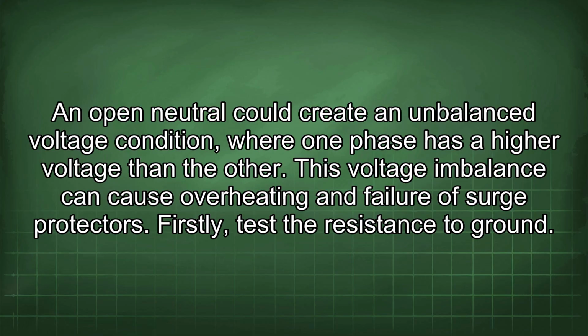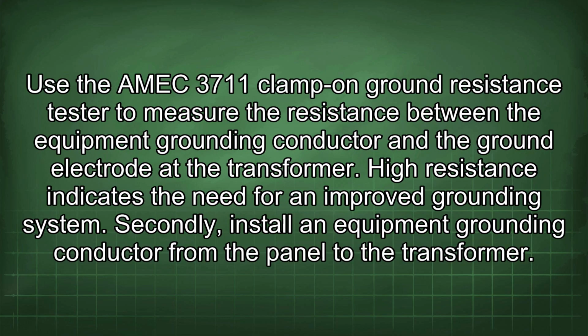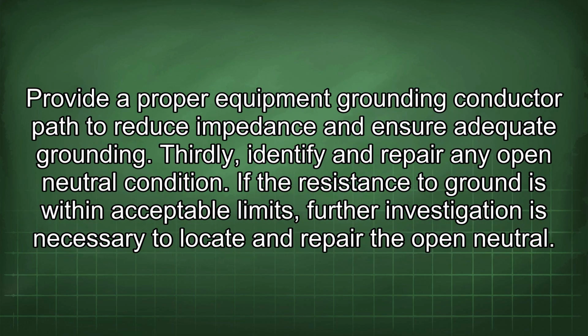Firstly, test the resistance to ground. Use the AMEC 3711 clamp on ground resistance tester to measure the resistance between the equipment grounding conductor and the ground electrode at the transformer. High resistance indicates the need for an improved grounding system. Secondly, install an equipment grounding conductor from the panel to the transformer. Provide a proper equipment grounding conductor path to reduce impedance and ensure adequate grounding.